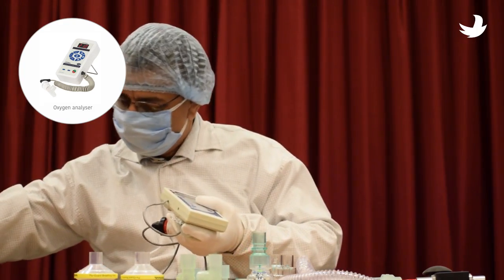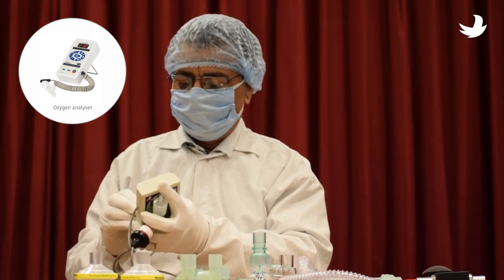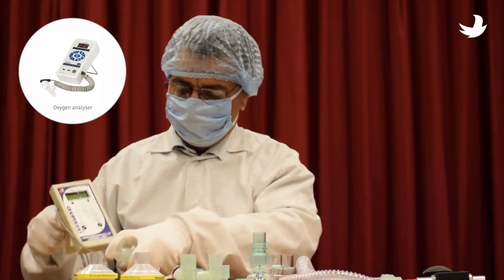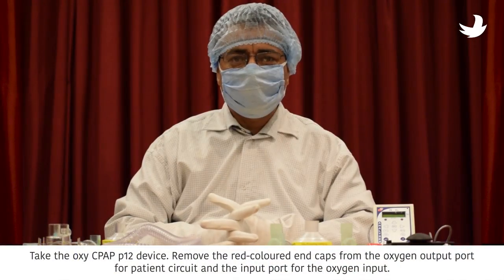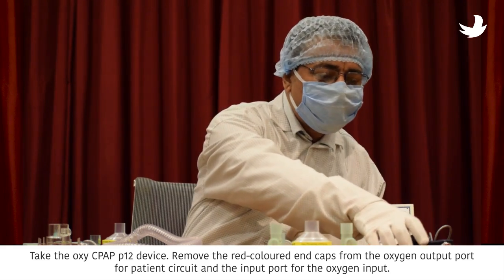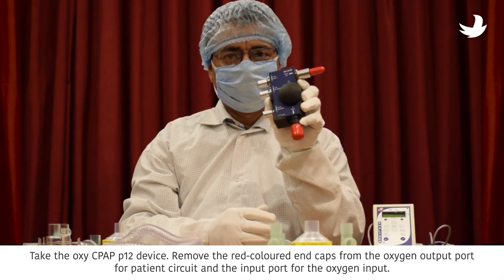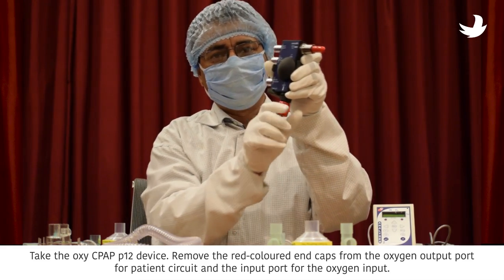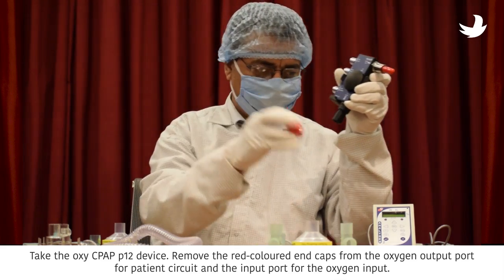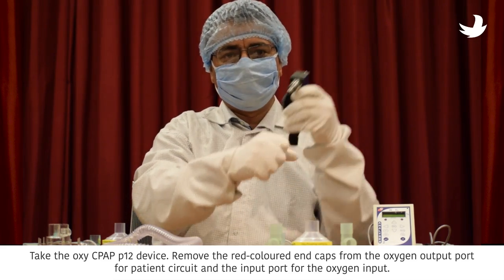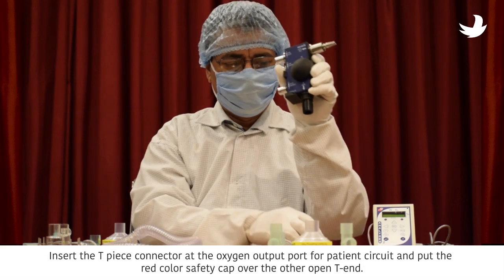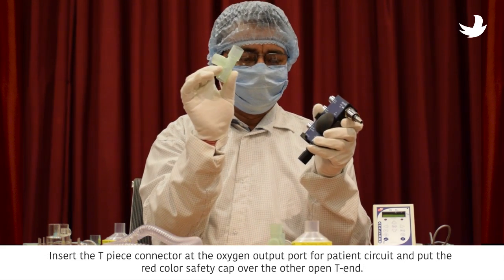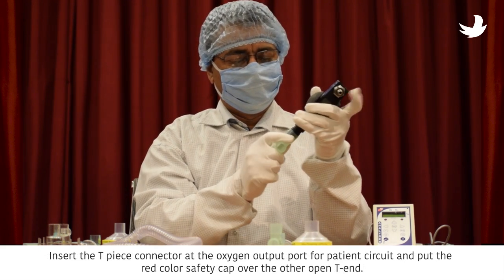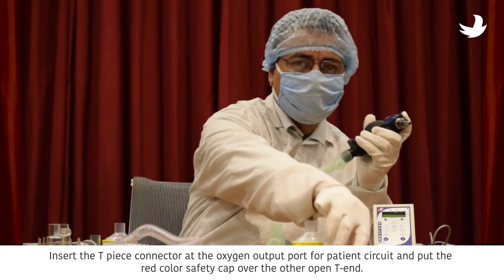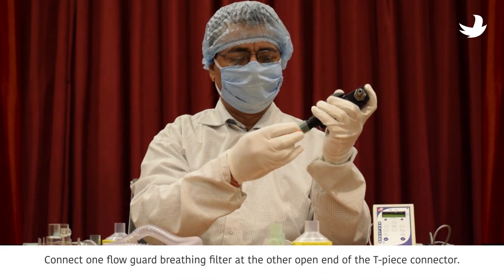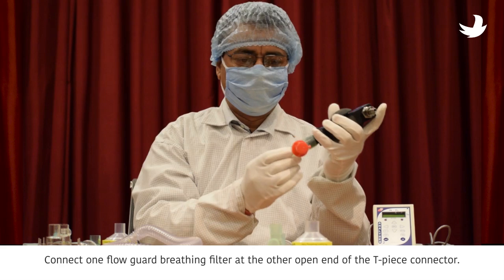calibration mode. So this is the complete set of the CPAP P12 device, the patient circuit assembly and the oxygen analyzer. Now we assemble the Oxy CPAP P12 completely. Take the Oxy CPAP P12 device. Remove the red colored end caps from the oxygen output port for patient circuit and the input port for the oxygen input. Insert the T-piece connector at the oxygen output port for patient circuit and put the red color safety cap over the other open T end.